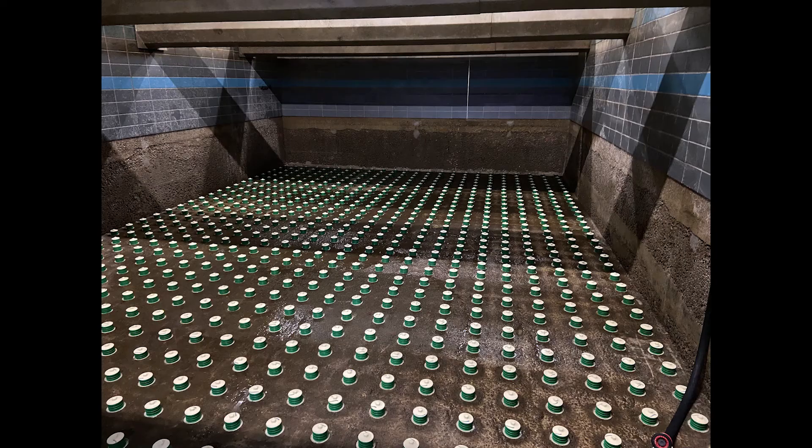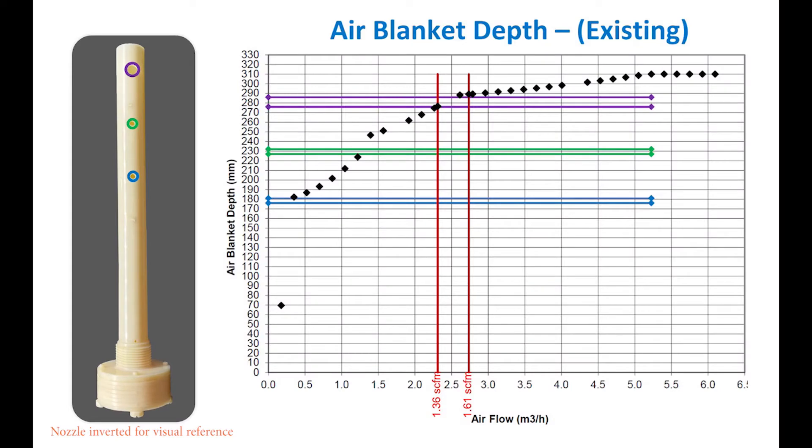Recently, Orthos was contracted to supply replacements of all nozzles at a competitor's problematic installation. We input the nozzle tailpipe dimensions into our model, which immediately raised a concern about the location of the air water divide line relative to the existing nozzles air metering holes.